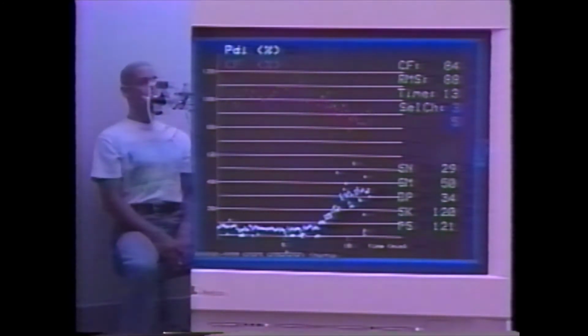Transdiaphragmatic pressure, expressed as a percent of the maximal voluntary transdiaphragmatic pressure, is presented in the lower trace in white. These values were obtained in this subject breathing for 7 minutes at rest, and then with progressively increasing inspiratory resistance. Center frequency of the EMG power spectrum reflects the action potential conduction velocity along the muscle fiber membrane and is known to decrease with increasing loads, which eventually lead to task failure. By following the diaphragm EMG center frequency, one can obtain early indications about diaphragm failure. On the right side of the screen, in numbers, are the simultaneous values of absolute center frequency, RMS, and the position of the diaphragm along the array. Signal quality is provided for every EMG sample obtained.